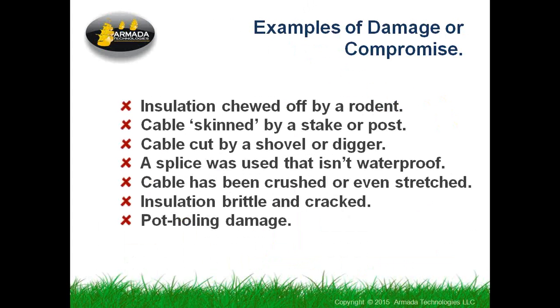Insulation chewed off by a rodent. In some parts of the country that's especially difficult because there are so many. Rodents like to tunnel along soft ground, and where you've buried pipes and wires is softer ground than around there. Especially true here in Arizona where I am, where the ground can be pretty hard, and gophers will want to follow the softest path. And as they go along a wire, for some reason they feel motivated to chew the insulation off. If it's a power cable, they get fried. If it's just a low voltage cable like the type we usually see, then it just remains damaged and maybe corroded.